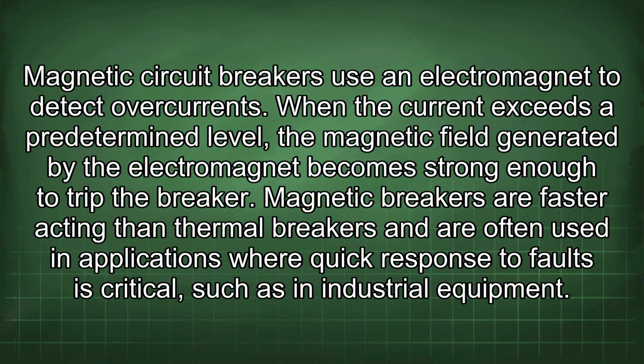Magnetic circuit breakers use an electromagnet to detect overcurrents. When the current exceeds a predetermined level, the magnetic field generated by the electromagnet becomes strong enough to trip the breaker. Magnetic breakers are faster acting than thermal breakers and are often used in applications where quick response to faults is critical, such as in industrial equipment.